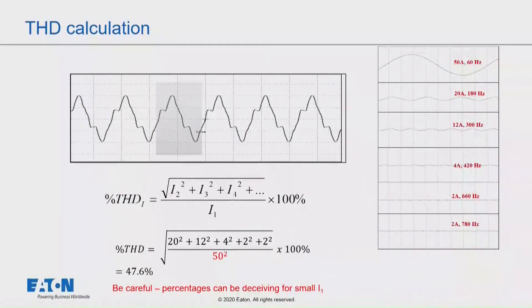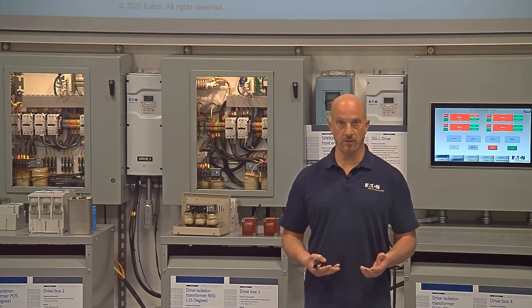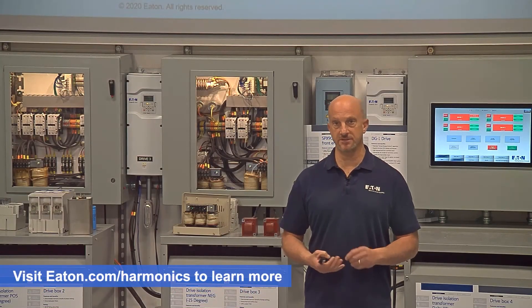But the percentage looks like it's through the roof. So I always warn people, don't get caught up in the percentages. The actual amps of harmonics are what's doing the work and doing the problems that you see in the power system, the overheating and so forth.